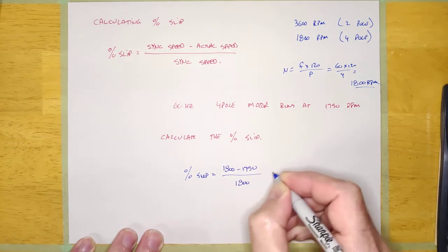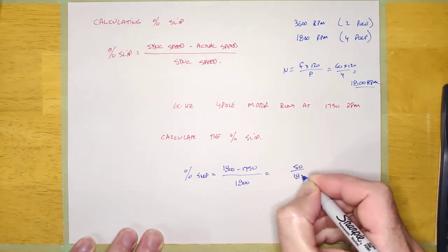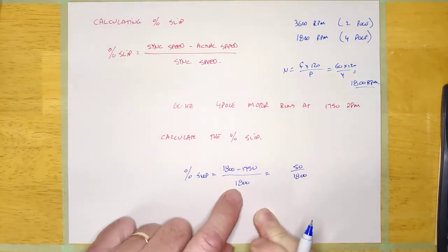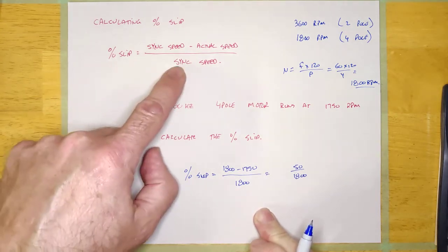So percent slip, it should be 1,800 sync speed minus 1,750 actual speed over 1,800, which is the sync speed, which is going to be 50 over 1,800. And really what this formula is doing is calculating the amount it's slipping and dividing it by the sync speed.